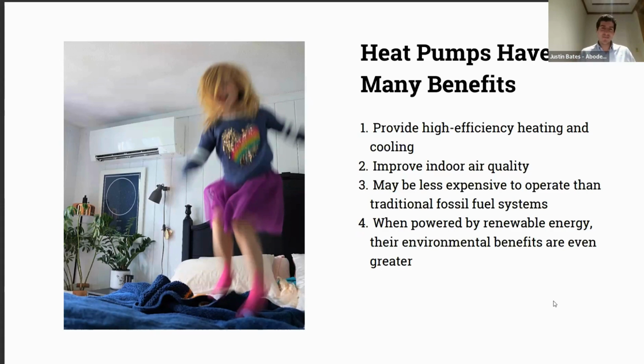They're losing energy, but heat pumps are different. Looking at two of the most popular models on the marketplace today from different manufacturers, at 47 degrees Fahrenheit, which is a rated temperature, they are 410 and 610% efficient. That's a huge difference, and that's where you start to see some of those savings on the operational side, that return on investment.